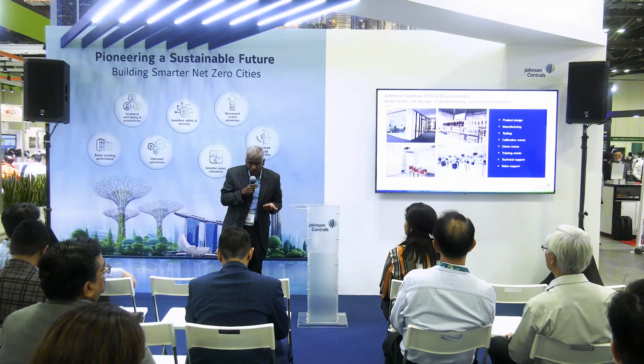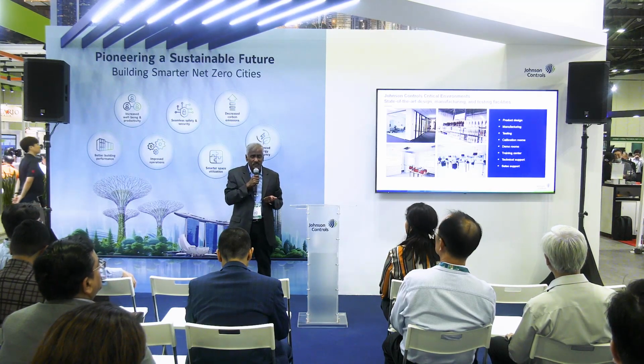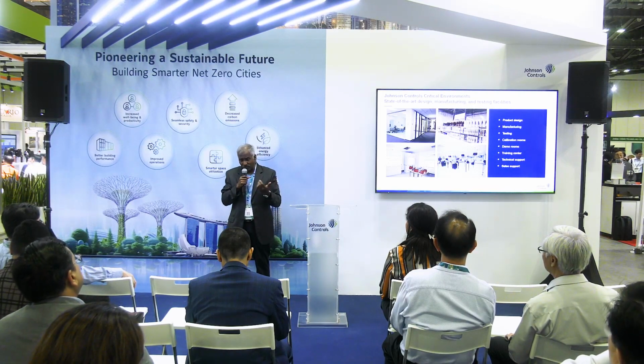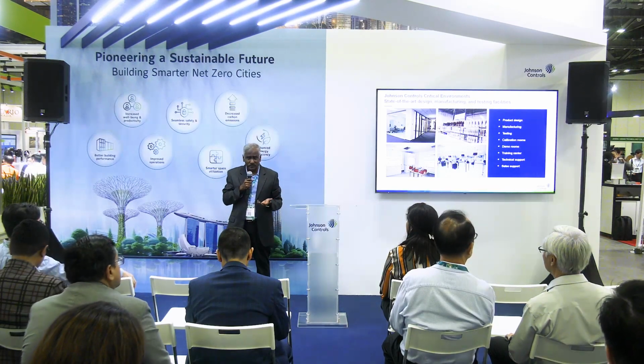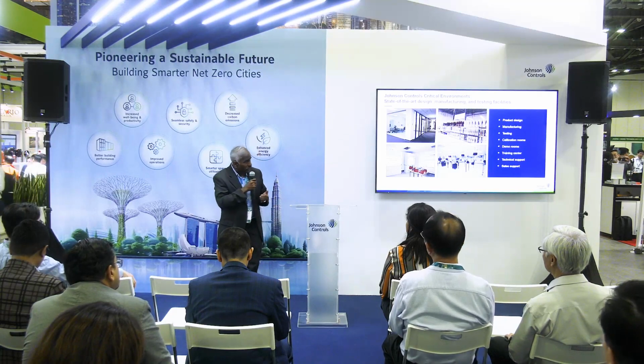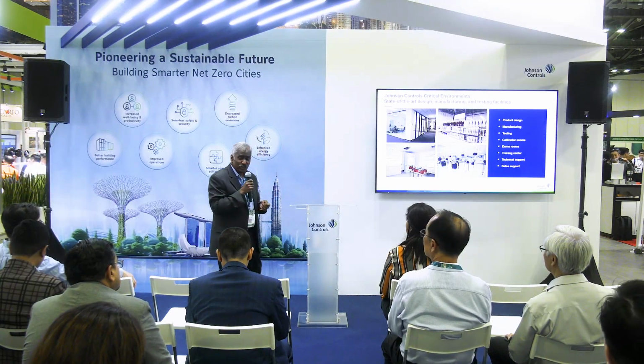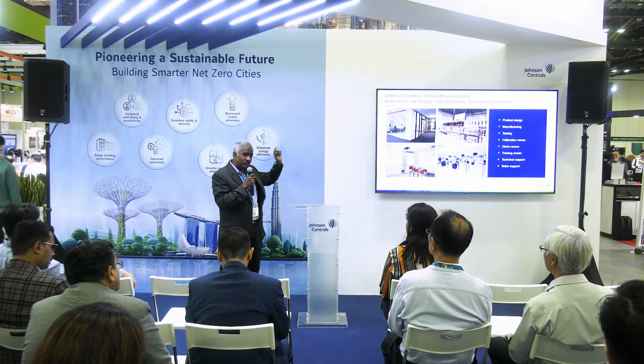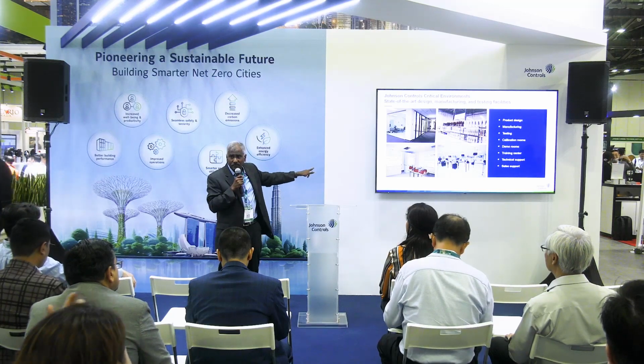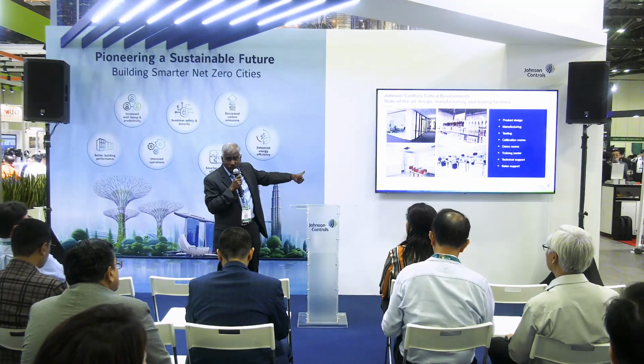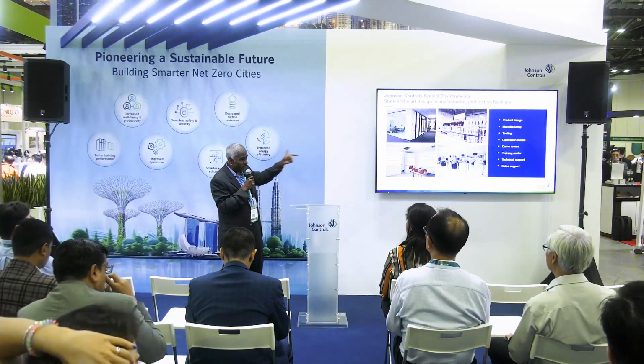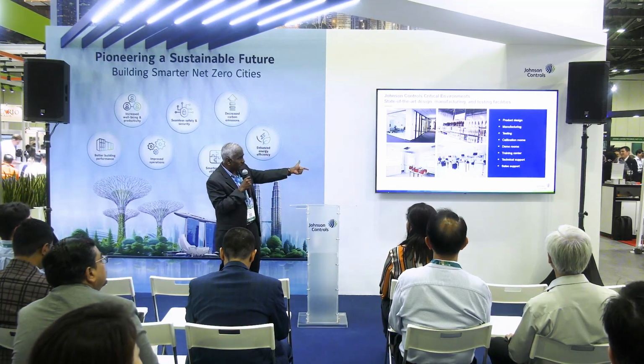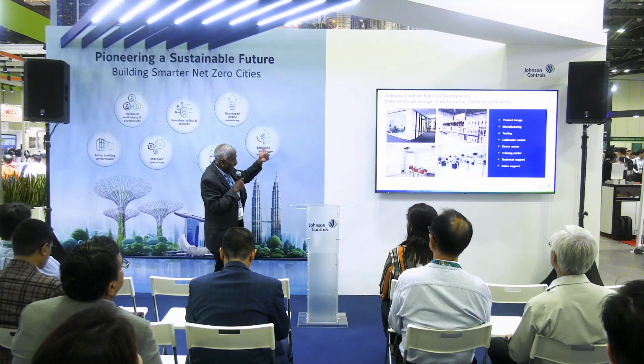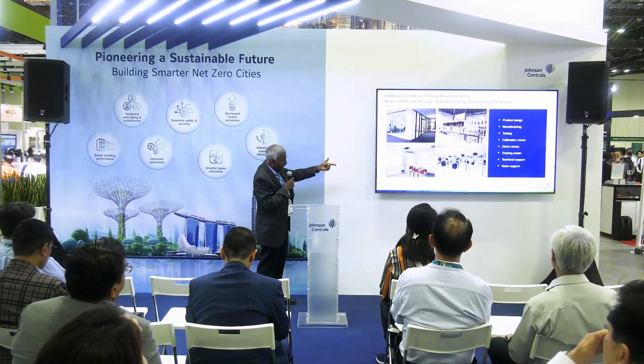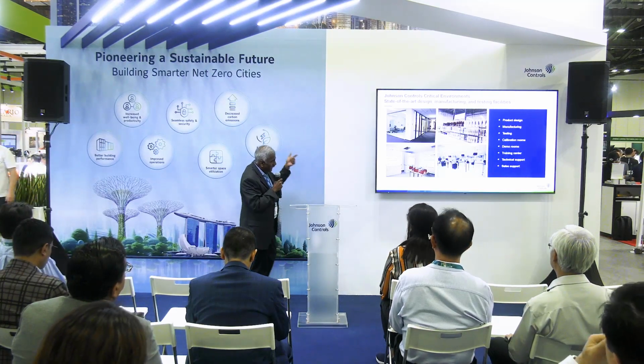Let's assume a customer or consultant has a purchase order for, let's say, 100 or 200 Venturi valves. Each and every Venturi valve has to be tested, because it's a critical environment. You need to make sure the right flow is there, and that it is maintained with variations in pressure. That's why we have good manufacturing processes where testing and calibration are done.